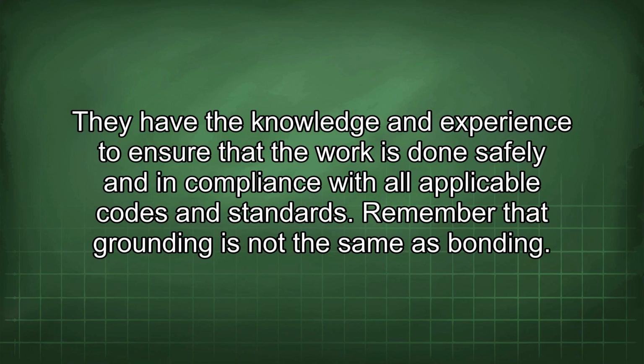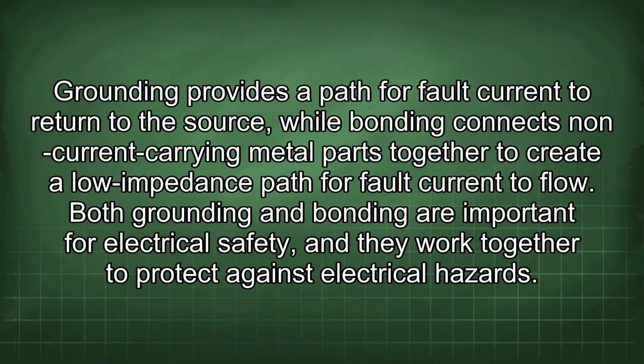Remember that grounding is not the same as bonding. Grounding provides a path for fault current to return to the source, while bonding connects non-current carrying metal parts together to create a low impedance path for fault current to flow. Both grounding and bonding are important for electrical safety, and they work together to protect against electrical hazards.